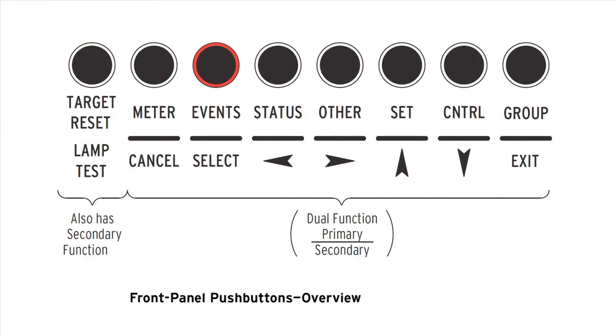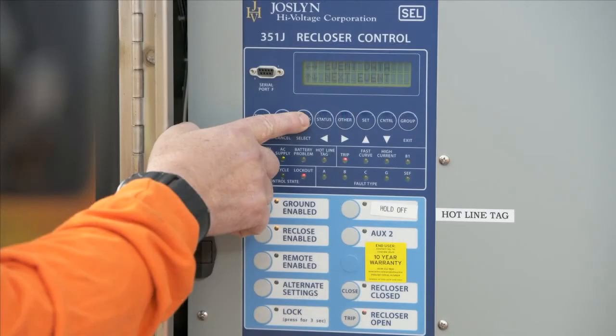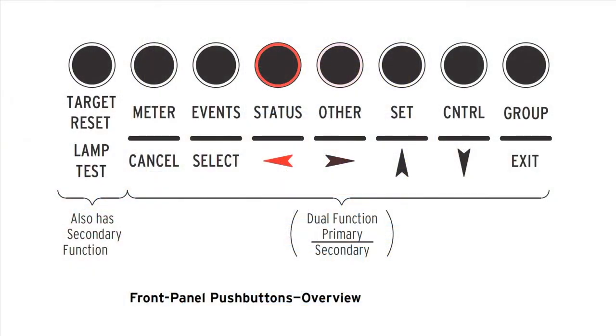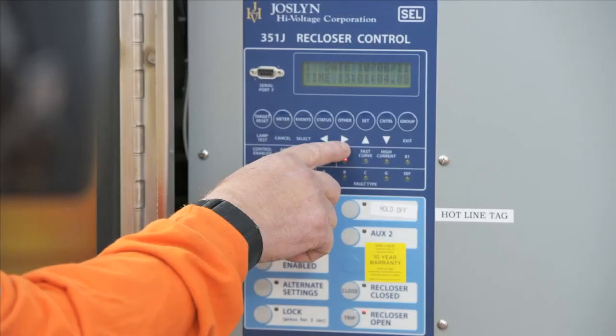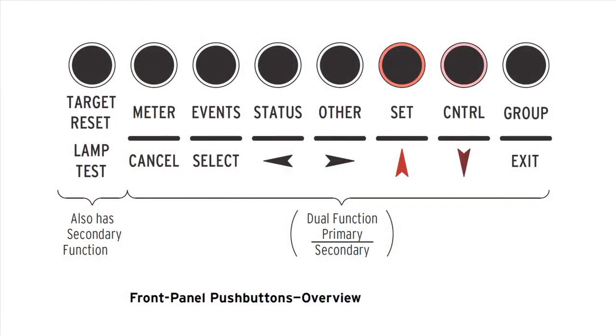Secondary functions. After a primary function is selected, the push buttons then revert to operating on their secondary functions. Use the left arrow and right arrow to underscore a desired function. Then press the Select push button to select the function. Use the left arrow and right arrow buttons to underscore a desired setting digit. Then use the up arrow and down arrow to change the digit. After the setting changes are complete, press the Select button to select or enable the setting.